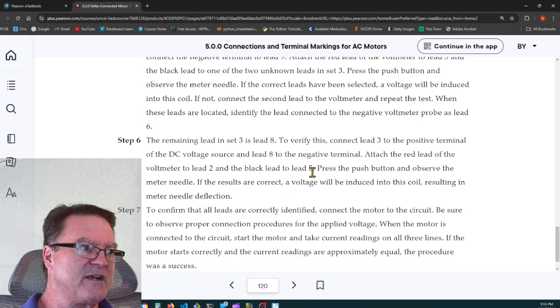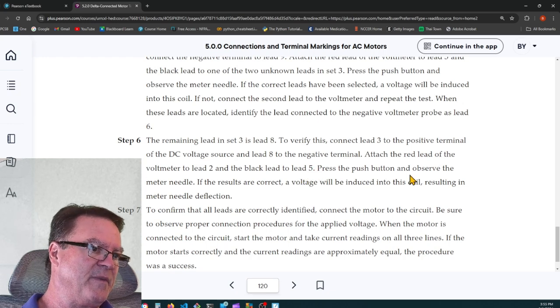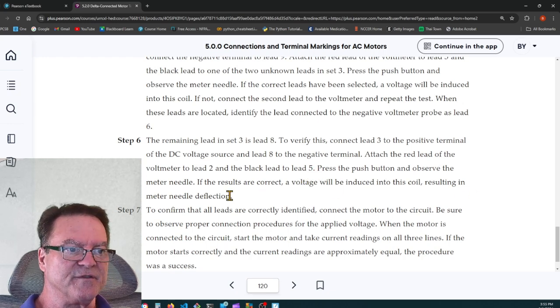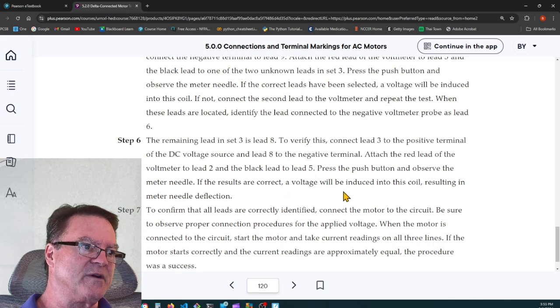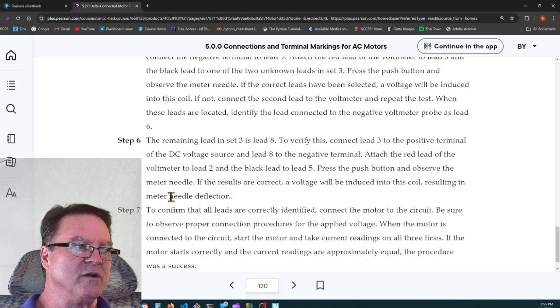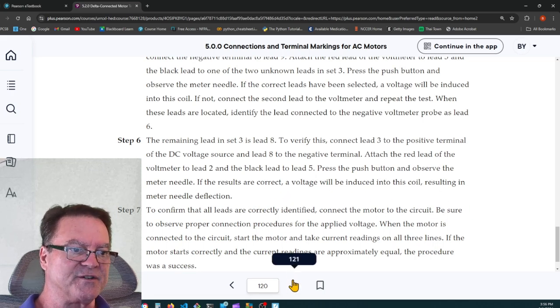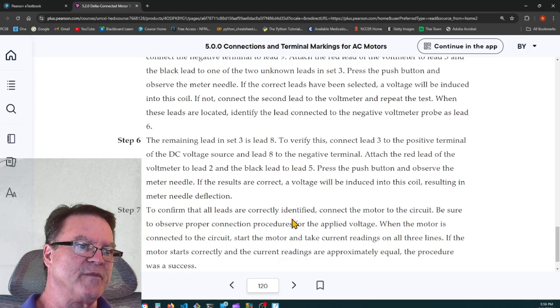negative terminal. Attach the red lead of the voltmeter to lead 2 and the black lead to lead 5. Press the push button and observe the meter needle. If the results are correct, a voltage will be induced into the coil, resulting in the meter needle deflection. And to confirm that all leads are correctly identified, connect the motor to the circuit. Be sure to observe proper connection procedures for the applied voltage.